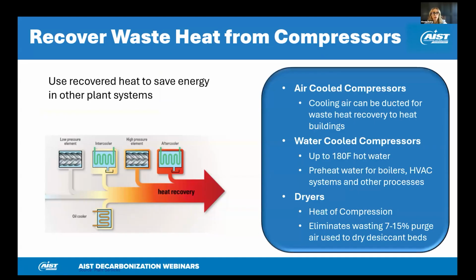We talked about waste heat recovery. There are 3 ways to go about this for a compressed air system. If you have an air-cooled compressor, you can look at ducting the cooling air to heat a building or a room. For water-cooled compressors, you can take the rise off that water manifold and preheat water for boilers or HVAC systems. In regard to dryers, I would say about 95% of compressors have a desiccant dryer following them in these steel mill applications. Installing a heat of compression dryer, I think, will give you the quickest ROI and capture that wasted heat and use it in a purposeful way.